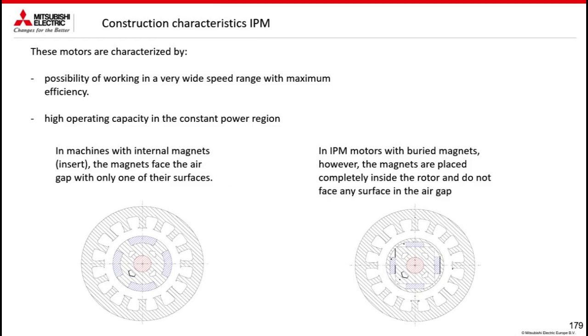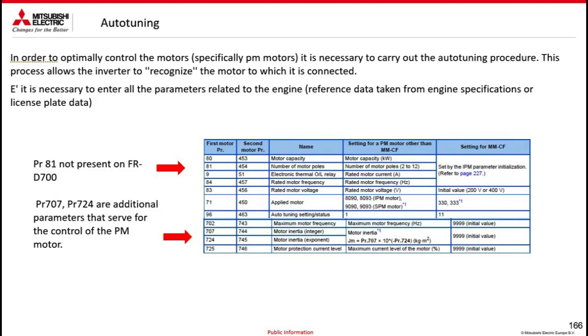The PM motors are divided into two categories: SPM motors, with surface magnets, and IPM motors, with internal magnets. As parameters, I have to define the nominal current in parameter 9 and the type of motor in parameter 71. In parameter 71, I will put 8090 or 8093 if the motor is an EPM, or 9090 or 9093 if the motor is an SPM. And obviously for the asynchronous motor, 3 or 13. If self-ventilated, 3. If servo-ventilated, 13.